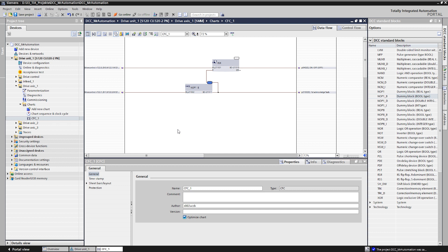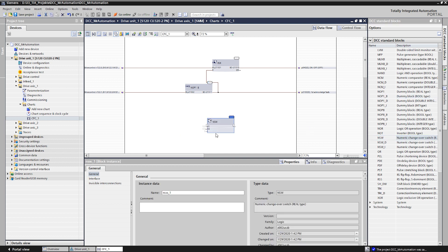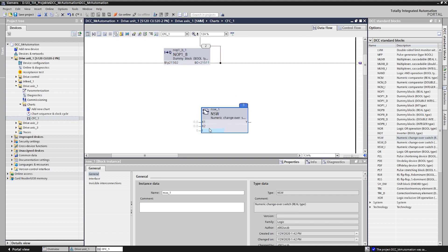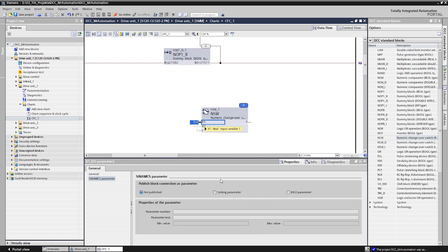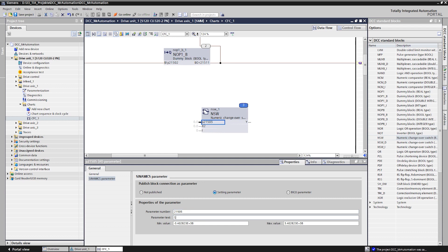For switching between two values, the numerical switch is available here. At this point, the inputs are not published as BICOs, but as setting parameters. We do not want to interconnect the inputs with other parameters, but rather be able to specify values for the different speeds here. In addition, minimum and maximum values can be specified for those setting parameters that cannot be undershot or exceeded. We select minus 6000 and plus 6000 speed limitation.